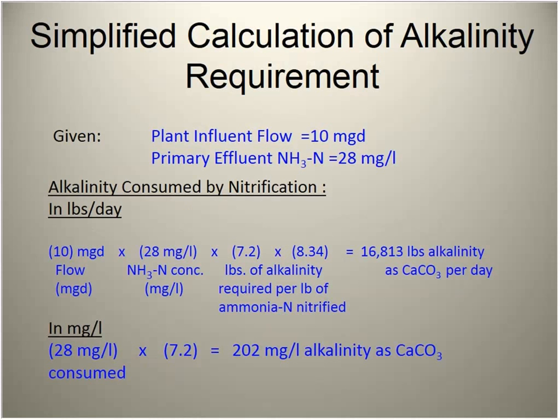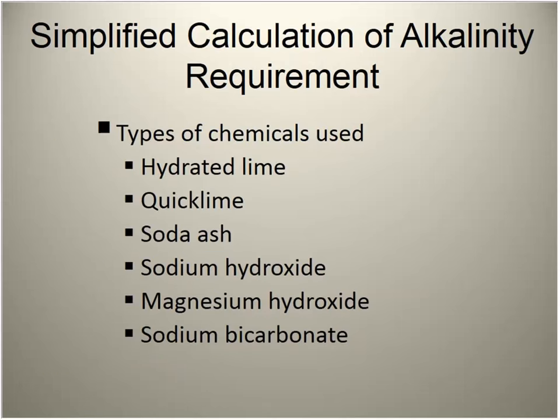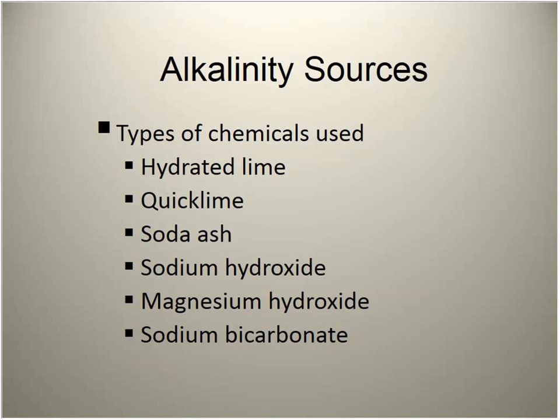For a 10 MGD plant with influent ammonia of 28 mg/L, requiring approximately 7.2 pounds of alkalinity per pound of ammonium, the calculation shows you need 16,800 pounds of alkalinity coming into the process, which works out to dosing 202 mg/L. Chemicals that can be used include hydrated lime, quick lime, soda ash, sodium hydroxide, magnesium hydroxide, and sodium bicarbonate.